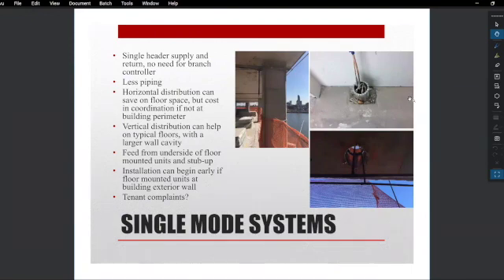And you can see on the pictures to the right, this is Cornell, and we had a dedicated ACCU on every floor that fed 2 floors on the south side, and then on the next floor we would have an ACCU that fed 2 floors on the north side. And the way we did this was we ran a refrigerant header around the perimeter of the building, either south or north, depending on what ACCU was. And then we would stub up to the floor-mounted fan coil unit that was along the perimeter of the building.